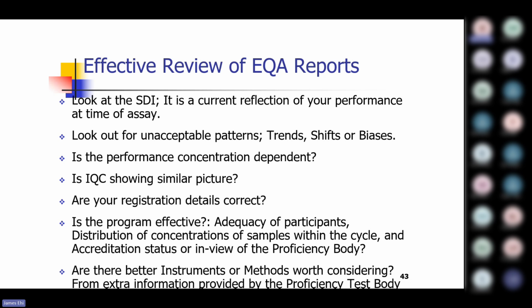Then look at your IQC also. Is the IQC showing a similar picture? If IQC is showing a similar picture, then you know that you have a systemic problem. It's not only affecting the EQA, it's affecting IQC, and it's invariably affecting patient results.